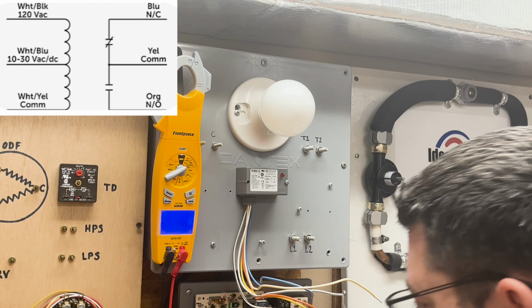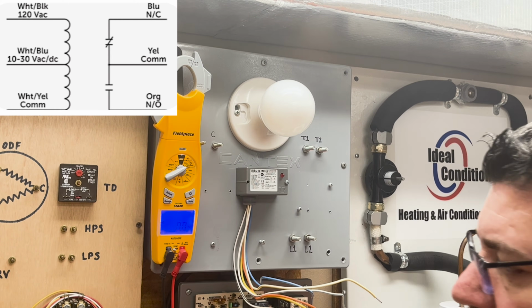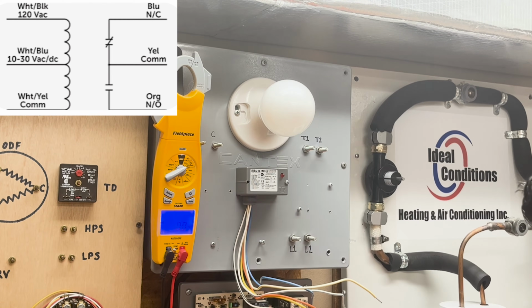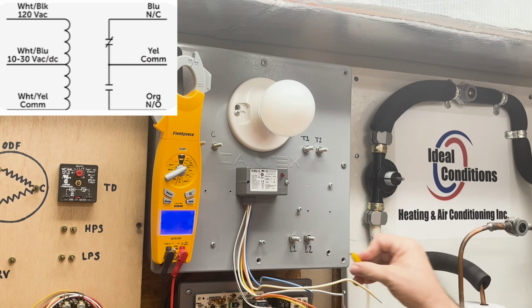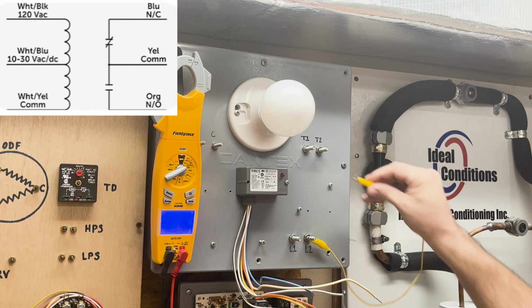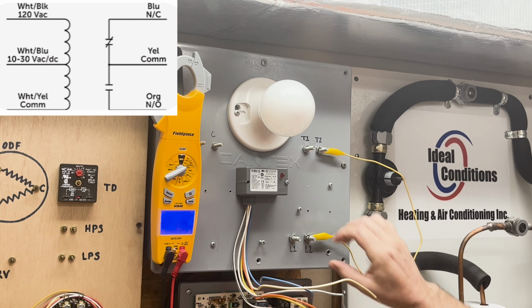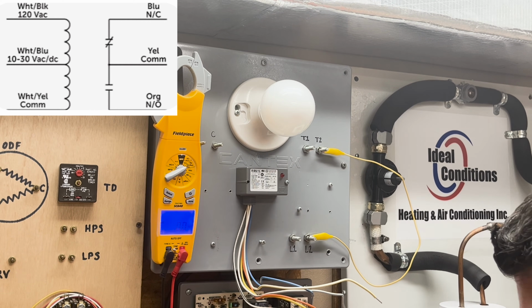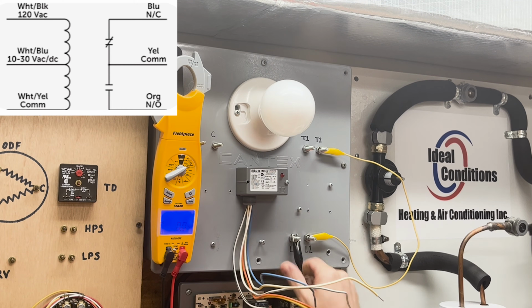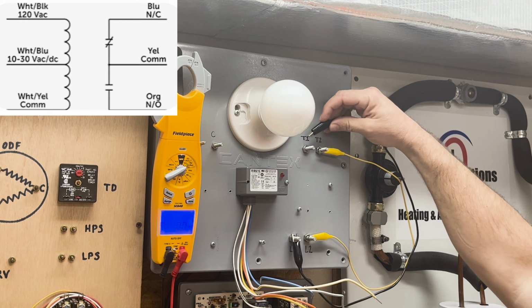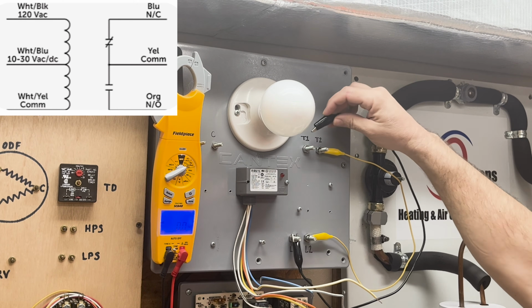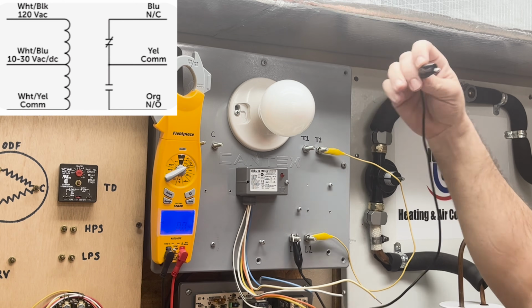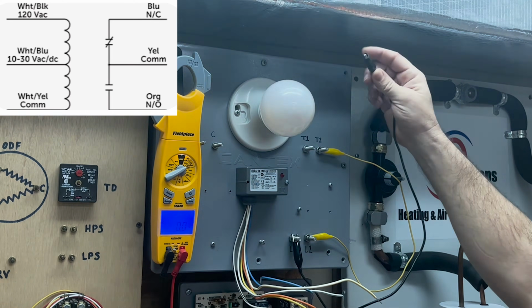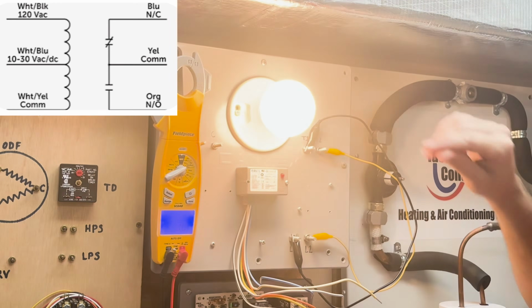This light bulb can represent a fan motor, compressor, anything that we want that's in the 240 volt world. Wiring it up without the relay, we're just simply going to bring line voltage up to each terminal. We have L2 to T2. And then we're going to bring L1 to T1. And I'm going to go ahead and touch it. And the moment I do, you'll hear the contactor inside the box click. And then the load will energize. Okay, so I'm just going to go ahead and leave that on there.